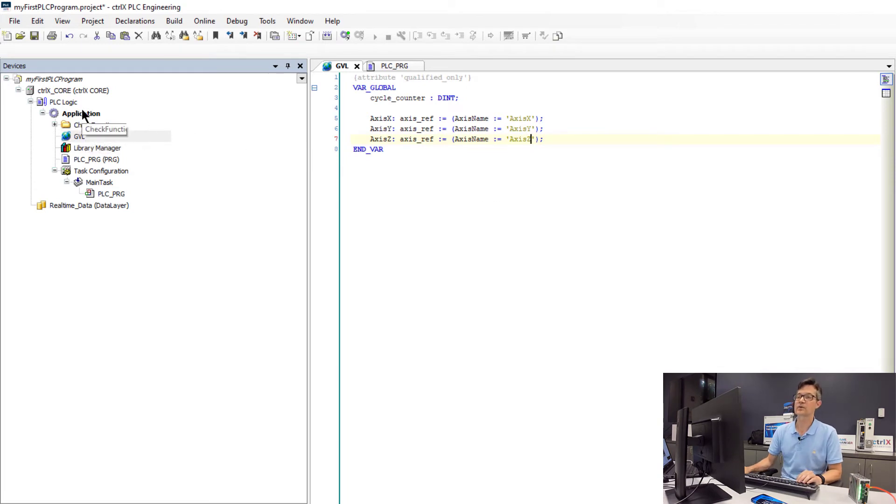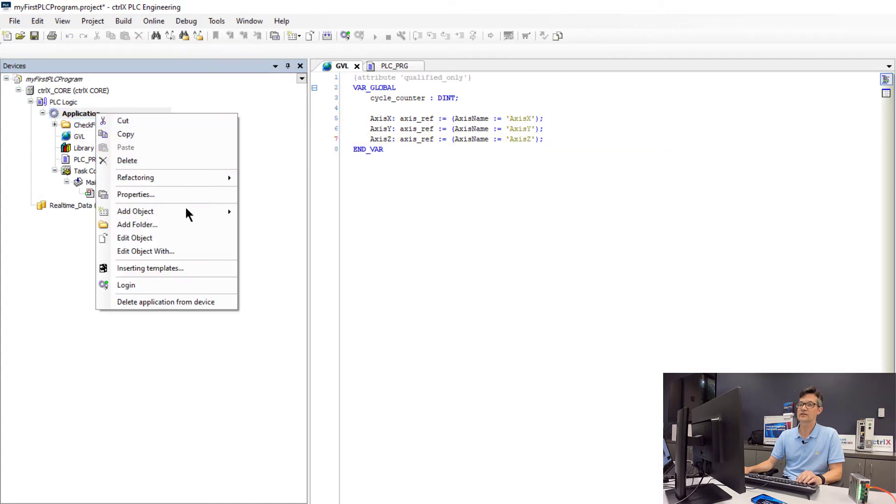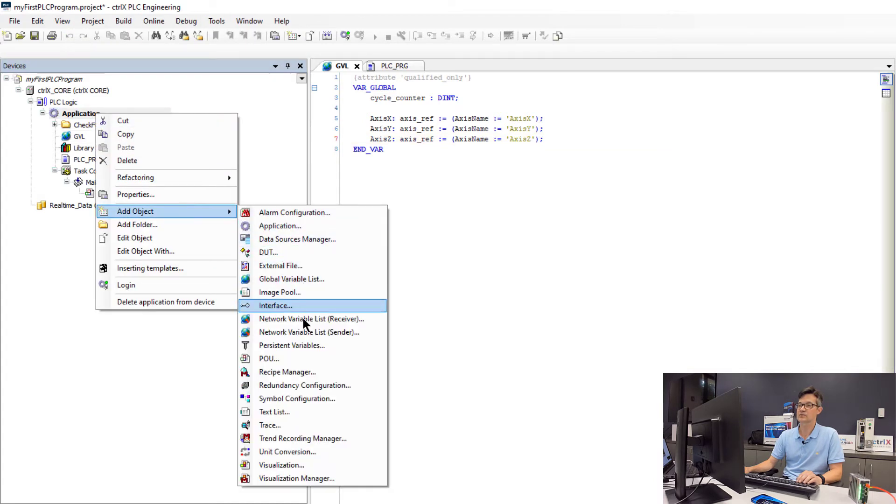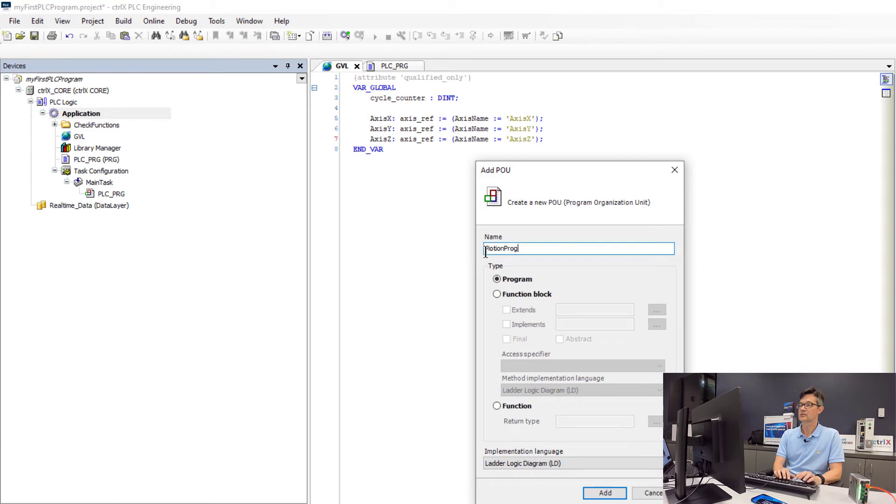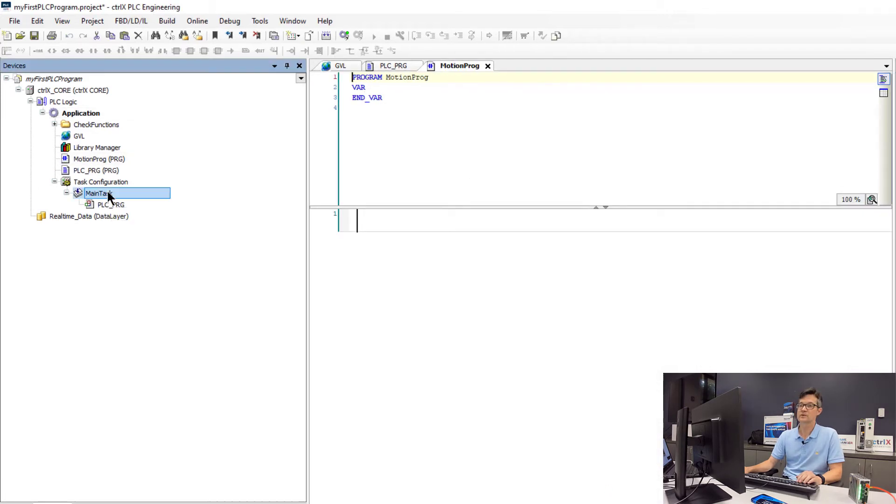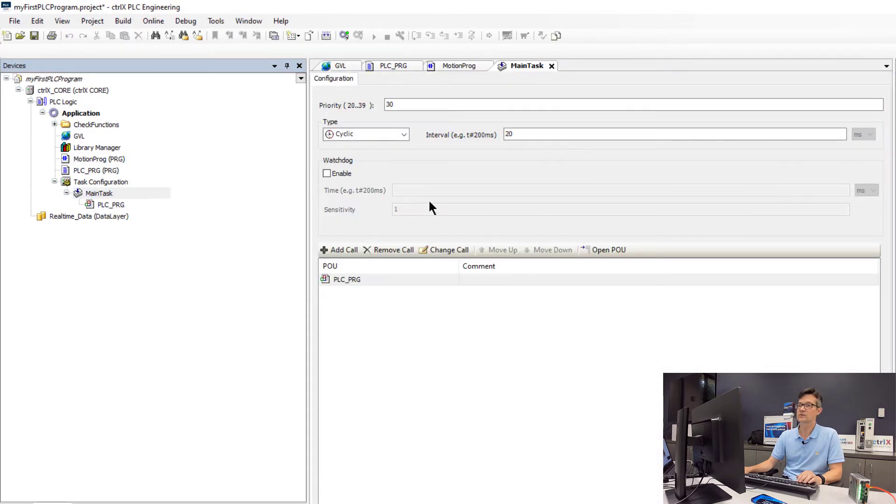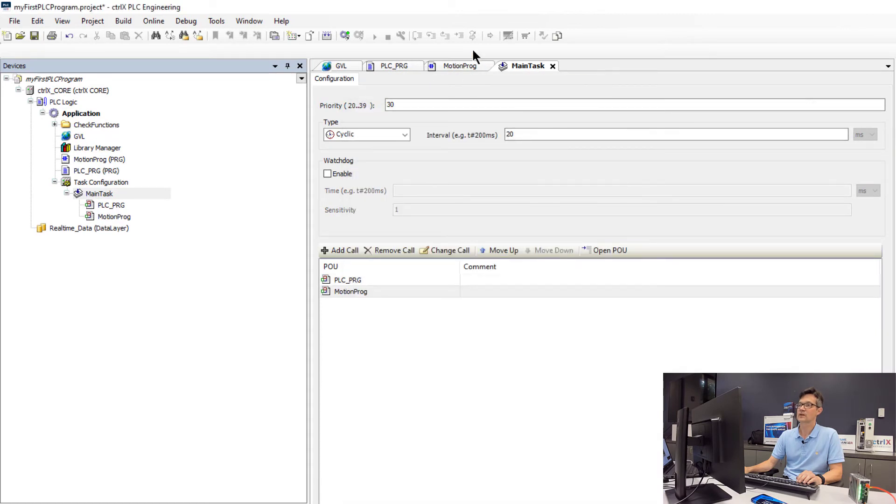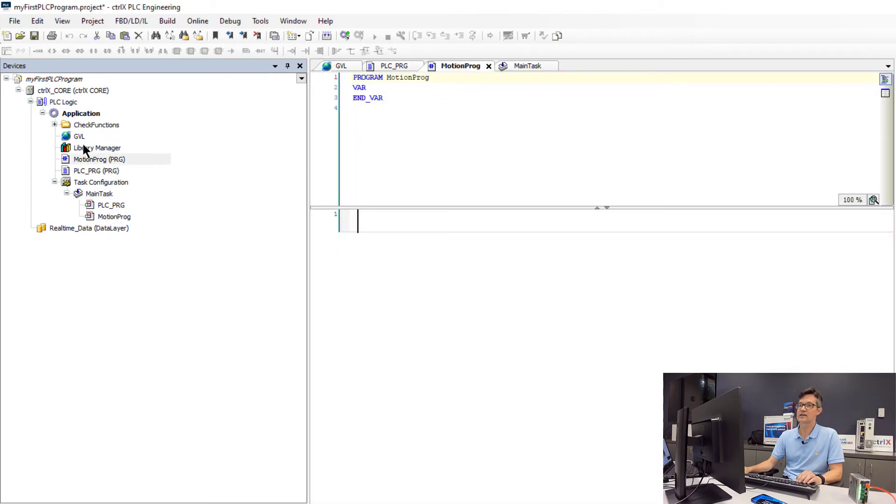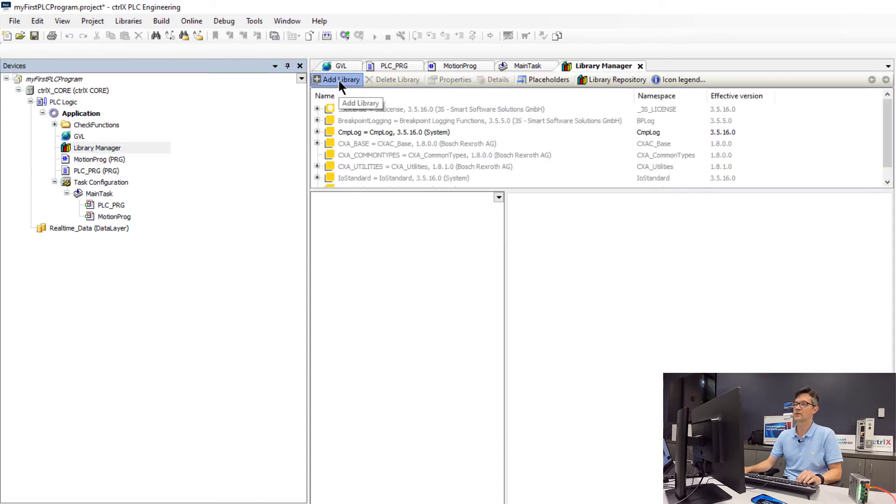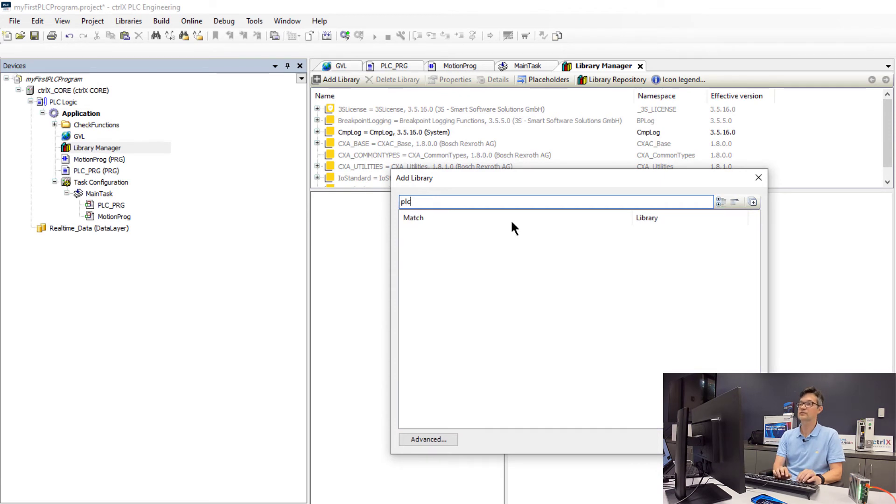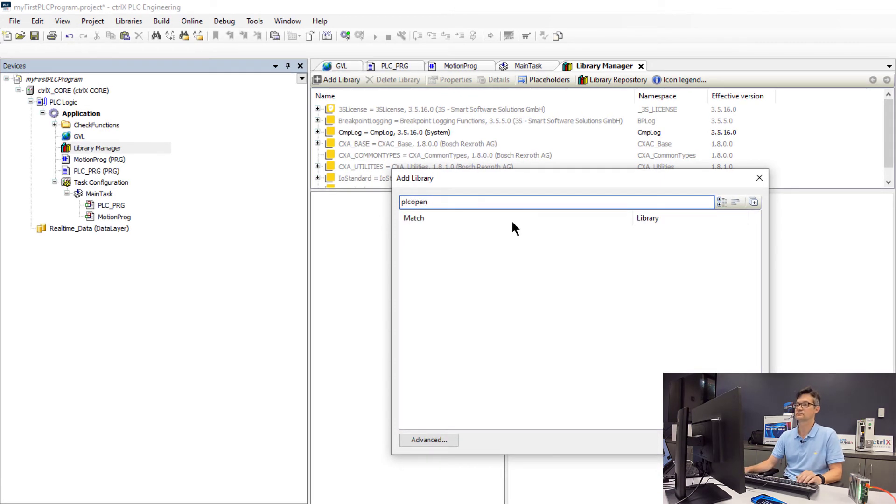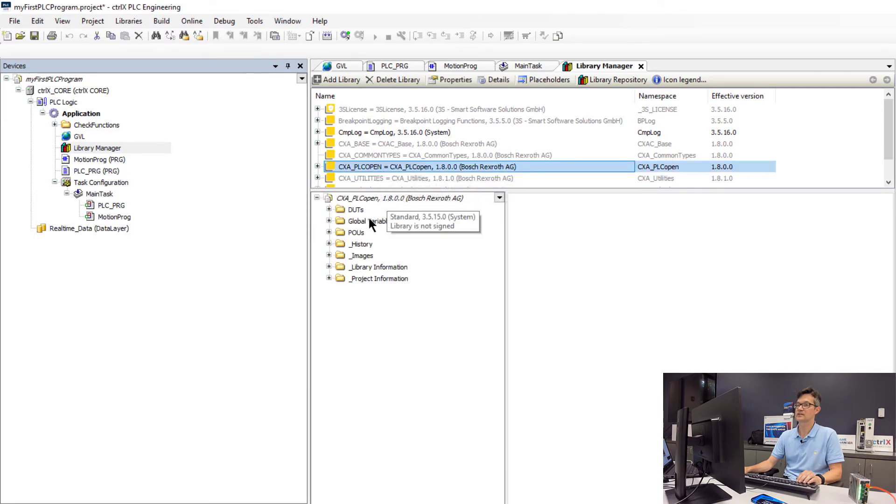So now we need to create a program which we will use to move our axes. We will go back to the application area and add another object which will be a POU. In this case we will call it motion prog and implement this one in ladder logic. The first thing we will do is schedule this program to be called in the main task. The next thing we need to do is add the library that gives us the function blocks to control the motion using PLCopen function blocks. We will add a library. A quick way is to search for PLCopen.